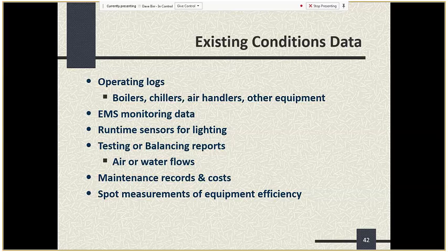When you went in originally, didn't you discover that a lot of the dampers and some of the chilled water valves were basically failed in open positions or not capable of being controlled by the existing EMS? That's correct. It's still an old pneumatic system, and we found quite a few air handlers where the pneumatic valve actuator had been removed, which out here in Hawaii left the chill water valve wide open.